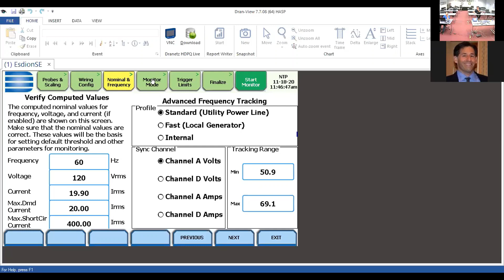Then we're going to go to monitoring mode. These are basically monitoring templates, and they're there to take a lot of the work out of setting up an instrument. Each one is related to a given type of monitoring scenario. If you didn't have these monitoring templates, you would pretty much have to set up the instrument from scratch every time you go out and perform a monitoring session. So these templates are merely shortcuts—they take a lot of the work out of setting up the instrument for a given application. You do have the ability, however, to go in and edit each of these templates to fine-tune a particular application. So the flexibility is there as well.